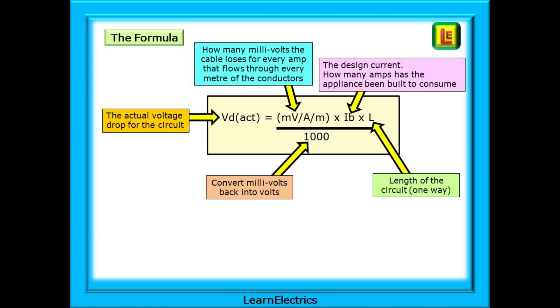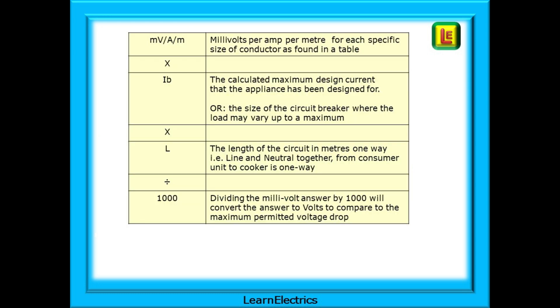Starting on the left at the nine o'clock position, we have the actual voltage drop that we are going to calculate for this circuit. Working clockwise, the equation itself begins with the blue box. Millivolts per amp per meter. How many millivolts the cable loses for every amp that flows through every meter of the conductors? Next, we have IB, the design current, and then L for the length of the circuit. And we convert millivolts back to volts by dividing by 1000. This table breaks down each of these steps. Millivolts per amp per meter multiplied by IB and multiplied by the length, then all divided by 1000. Pause the video and follow the steps.